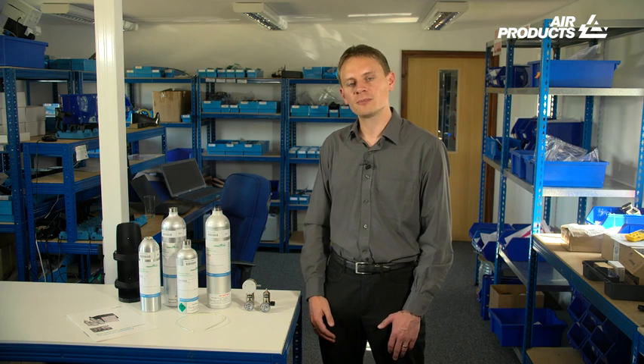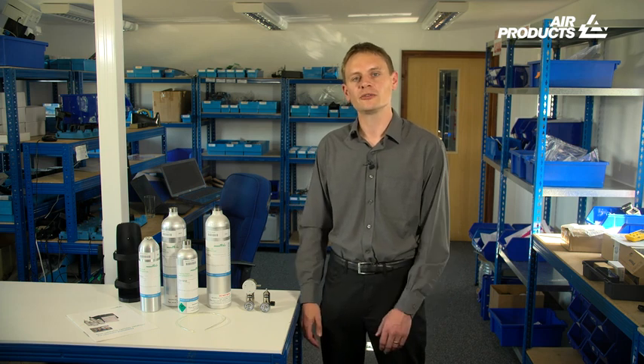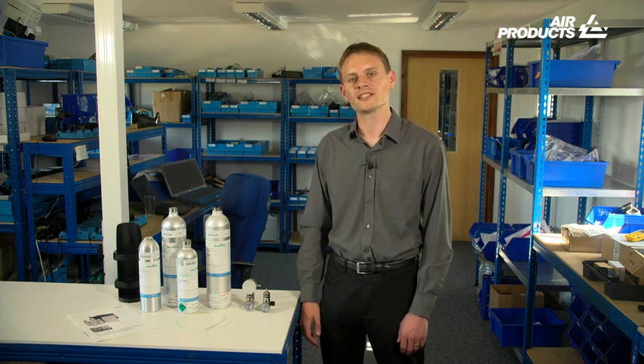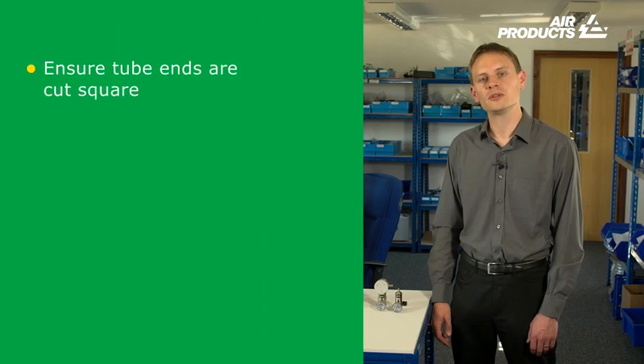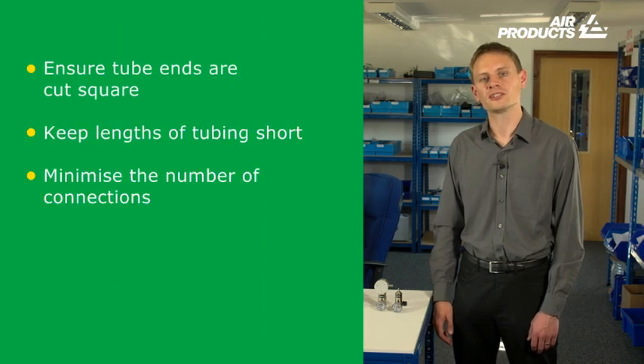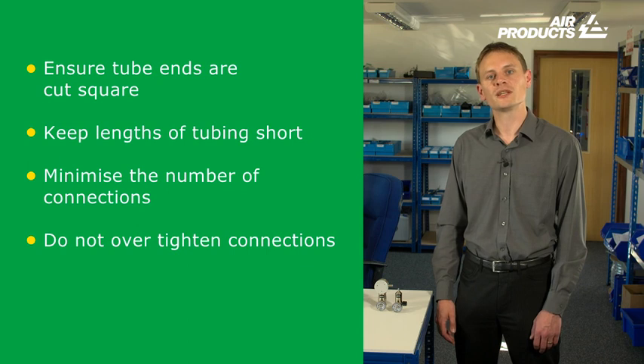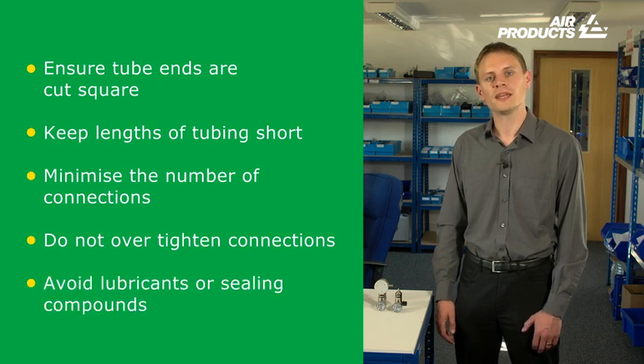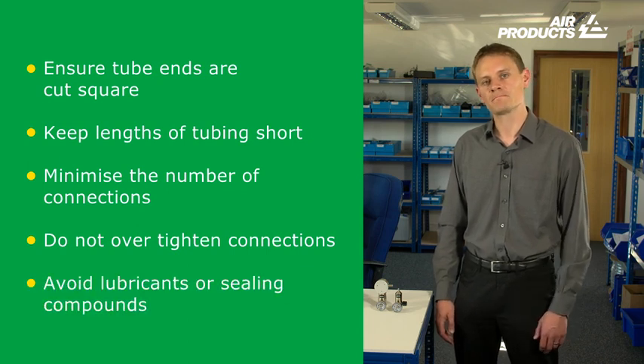So an instrument with a response time of 10 seconds using a fixed flow of gas of 1 litre per minute might be tested several hundred times using this type of canister. How can you ensure the same high quality gas from the canister reaches the instrument? It's important to consider the integrity of the system that delivers gas to the sensor. Every tube, joint and connection represents a potential leak point. So examples of good practice when making connections are listed here.